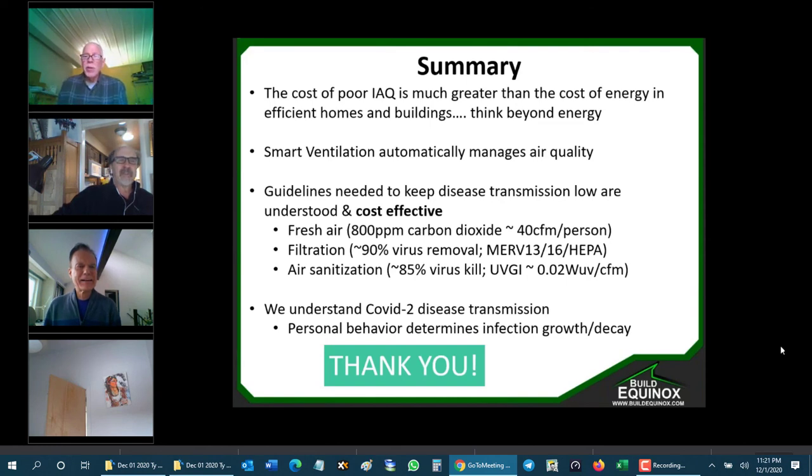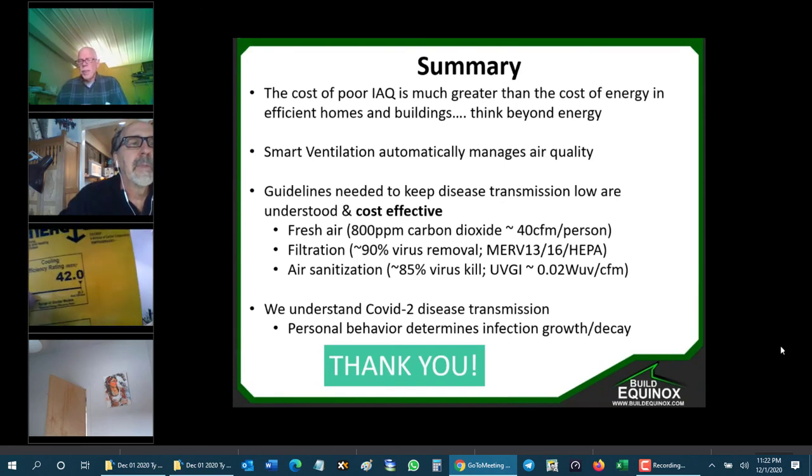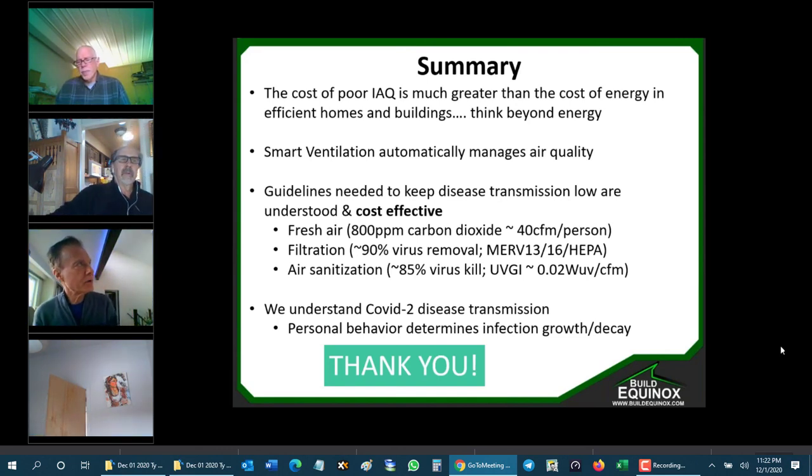But look up that report, Mini Split Madness, in that article, and that's got a number of those details. Okay, thanks. So Bob, I'll add some real world numbers. I have this Carrier 42 Seer, and it seems to have three levels. It's usually in winter time putting out between 90 and 105 degrees on the low zone, and it's pulling between 200 watts and 500 watts.